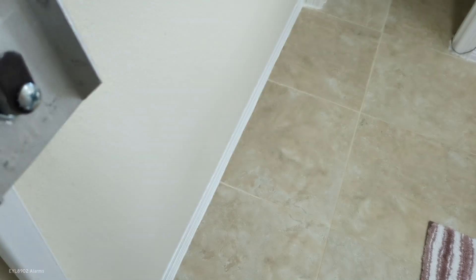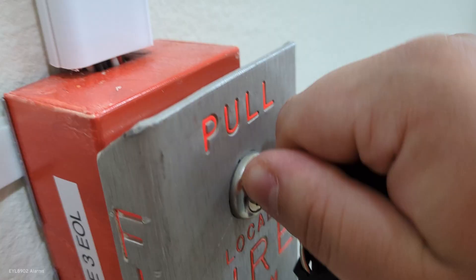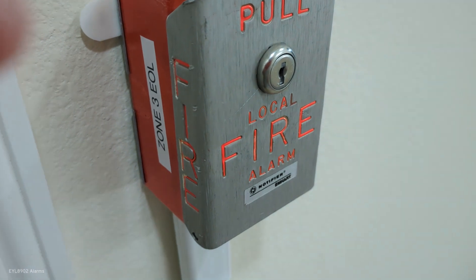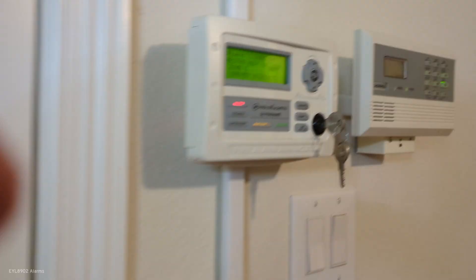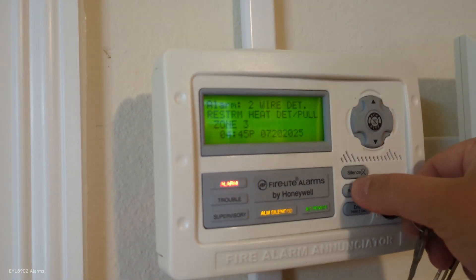That's that. We'll reset the pull station, reset again, and we'll test the heat detector. I did actually fix this pull station up there — I remember saying that — putting a key lock and everything in the switch. Works perfectly now. We'll go ahead and reset the heat detector.